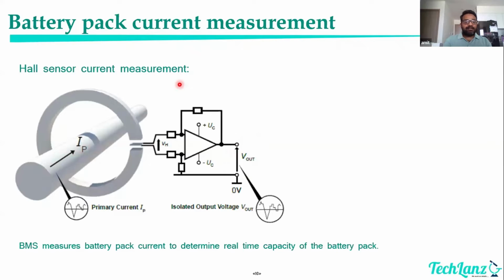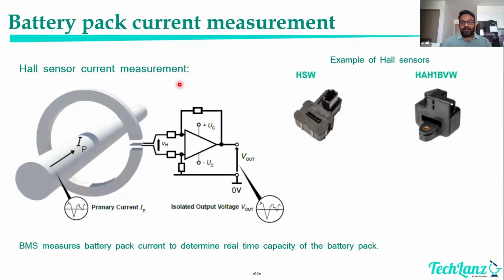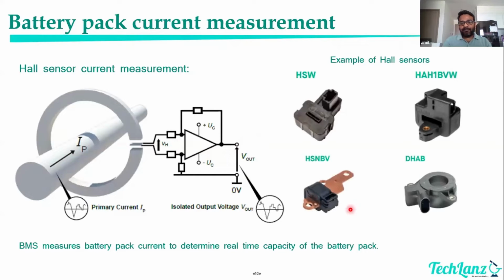Some examples of Hall effect sensors can be seen here - there are 4 different types, each with a slot built inside. Through this slot, a copper bus bar will pass, and inside the sensor there is an amplifier circuit built in. Through this amplifier circuit, the BMS reads the voltage coming out from the sensor, which is proportional to the current flowing through the bus bar passing through the Hall effect sensor.